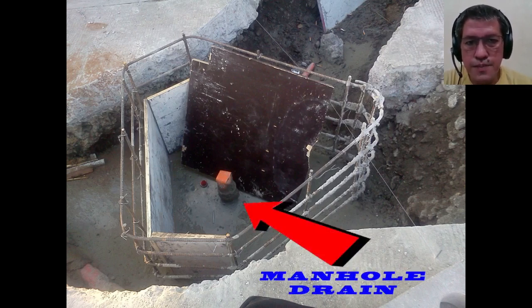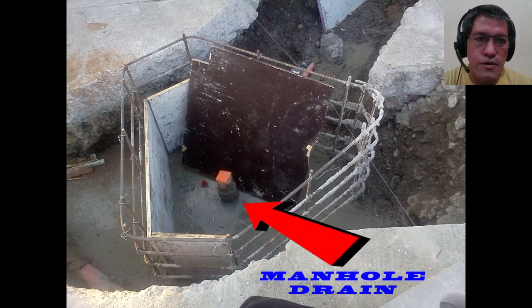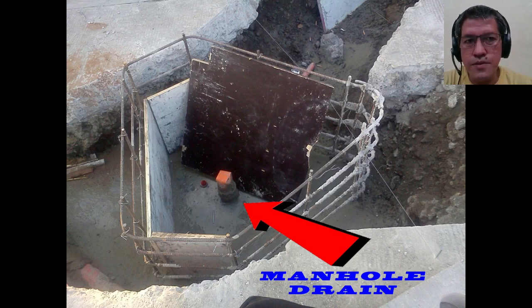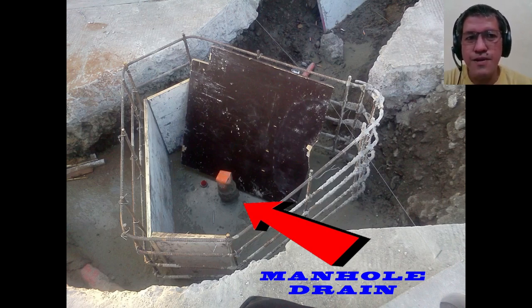This pipe here is actually the manhole drain, which is required in all manholes by standards — whether electrical or plumbing. The purpose is obviously so that water that comes into the manhole can flow out through this drain; otherwise the entire manhole would fill with water during heavy rains.